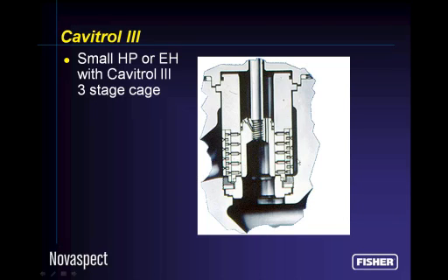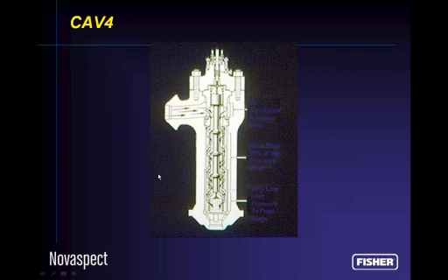In essence, I've created 3 valves in series here, the goal being to get successive pressure drops, each with a recovery, such that the last pressure drop does not drop below the vapor pressure. We can do this with many different architectures. The more severe the conditions for your valve, the more expensive the valve becomes, the more elaborate the valve trim becomes. But nevertheless, we valve manufacturers have valve trims and valve styles that are appropriate to the kind of differential pressures you want to throw at us.